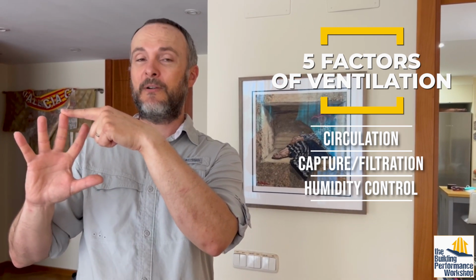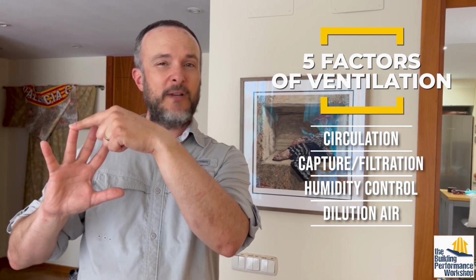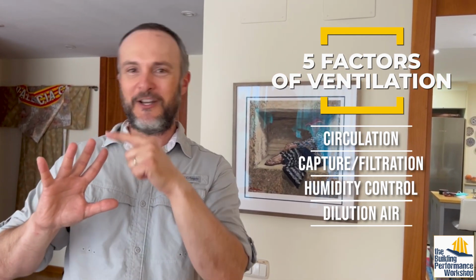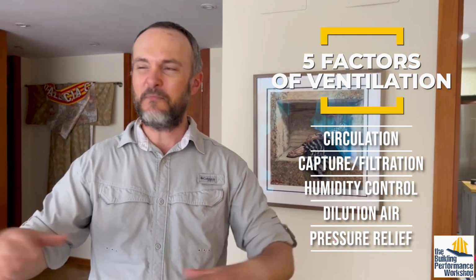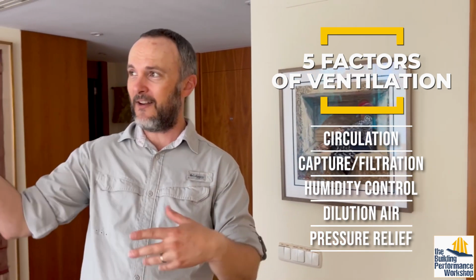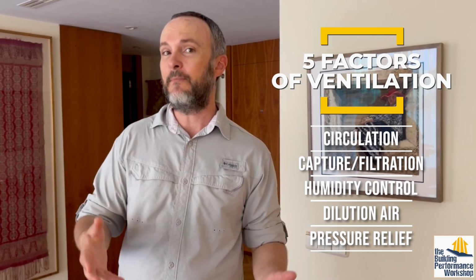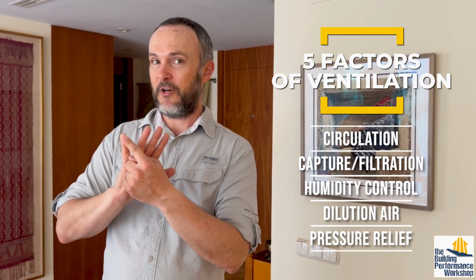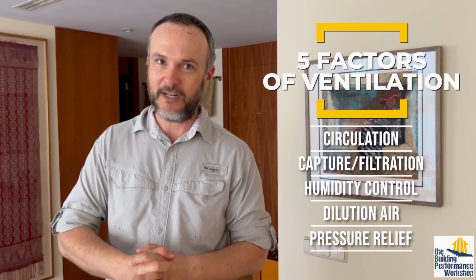Humidity control, super important in a climate like this. We don't have much of it. Dilution air, which you can have plenty of if you just open the windows, but again, how you do that as far as filtration and humidity control becomes an issue. And then pressure relief, which in this home, because it's probably leakier, although I will say that all of these buildings that we're seeing here in Spain are built with concrete, which is very easy to get pretty airtight. So that can be an issue. And remember, don't trust code on pressure relief as well. You need makeup air probably a lot sooner than a 400 CFM kitchen exhaust hood. Just my little PSA on that.